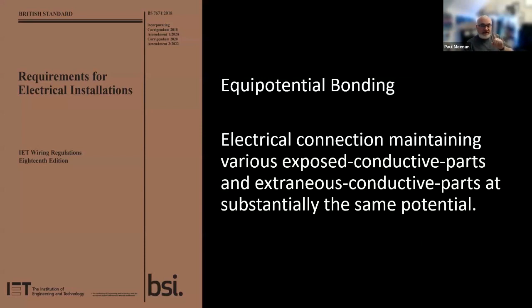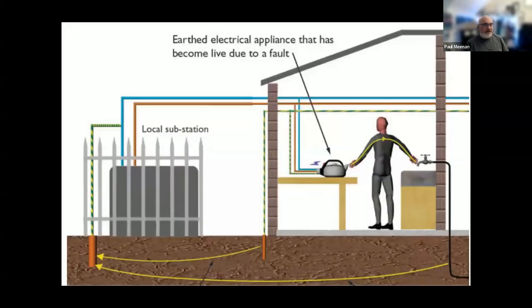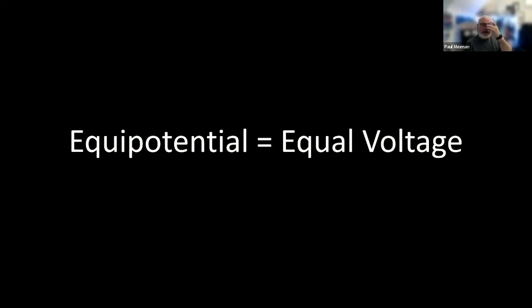And equipotential bonding, or equal voltage, is the electrical connection maintaining various exposed conductive parts and extraneous conductive parts at substantially the same potential. We keep using the word potential, and it's my personal opinion it should be deleted and we should just use the term voltage. So if you look here, you have an installation, an electrical appliance that's become live due to a fault, and that person there could be touching a water pipe which is brought in from the outside. Now the kettle is an exposed conductive part. It's exposed metalwork, forms part of the installation, generally expected not to be live but could become live. And the extraneous conductive part is very similar, but it's generally considered 0, and it could become live. It also could help form a path. As you can see, the path of fault could go through the gentleman who is undergoing that fault condition. Now, simply put, equipotential, equal voltage.